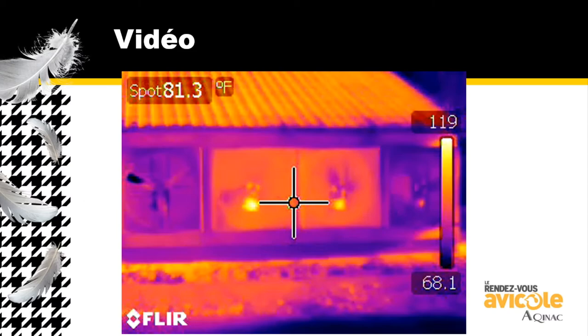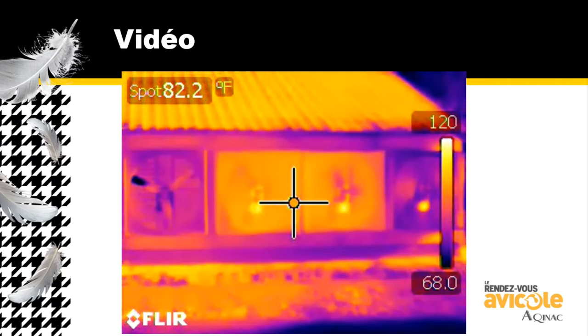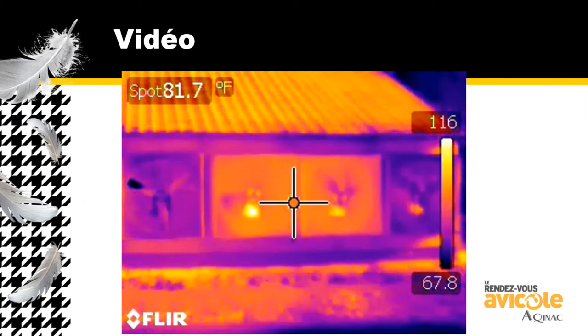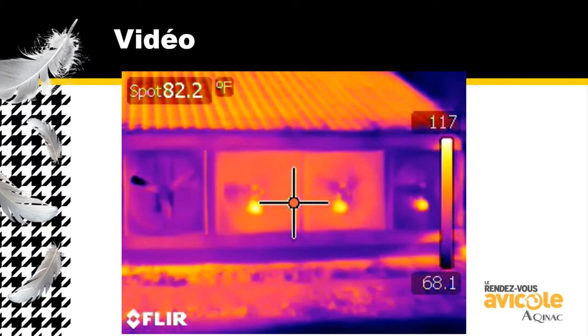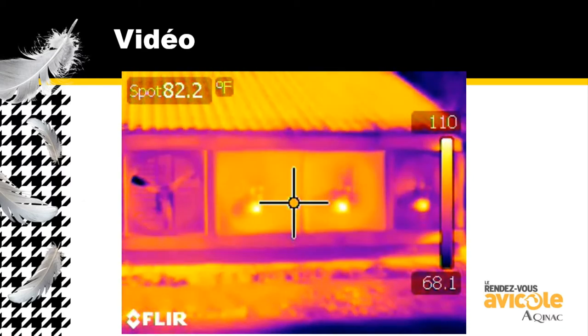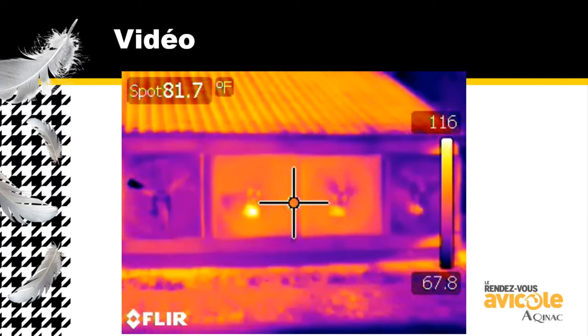Here's another video of houses going through the feeding operation. You can see there are four fans in this particular house. All three of the four fans are actually moving air — fan number one is completely off. But look at fan number four: is it pulling much heat out of the house? Not much at all. You can see the motor's running, but it's just not extracting as much heat as the others.